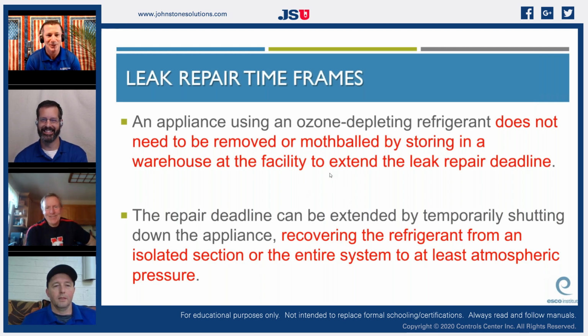A big cloud over that building. Yeah. Can you imagine what those two 32-inch diameter exhaust fans looked like coming out of the top of there when that leak sensor went off? Yeah. I can note one thing too. That's a cumulative leak rate, so over a year. Over a year. So if you lose 100 pounds in the first week, and then 100 pounds the next week, that adds up toward that 125%. You betcha. Right.